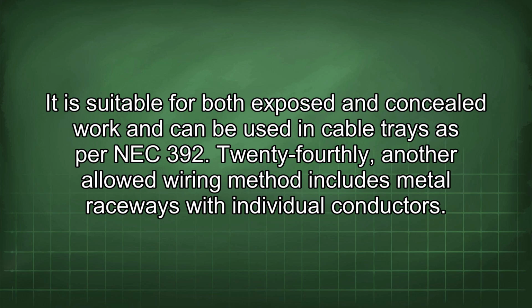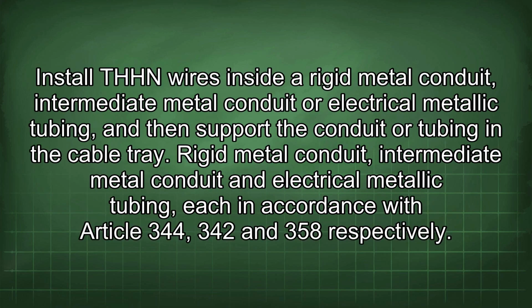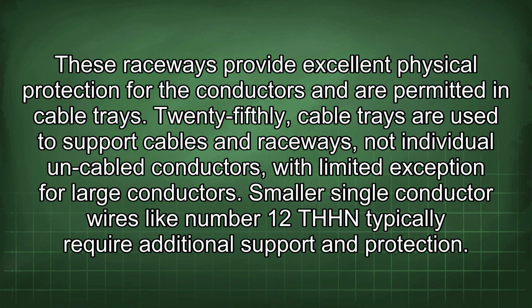24thly, another allowed wiring method includes metal raceways with individual conductors. Install THHN wires inside a rigid metal conduit, intermediate metal conduit or electrical metallic tubing, and then support the conduit or tubing in the cable tray. Rigid metal conduit, intermediate metal conduit and electrical metallic tubing, each in accordance with Articles 344, 342 and 358 respectively. These raceways provide excellent physical protection for the conductors and are permitted in cable trays. 25thly, cable trays are used to support cables and raceways, not individual uncabled conductors, with limited exception for large conductors. Smaller single conductor wires like number 12 THHN typically require additional support and protection.